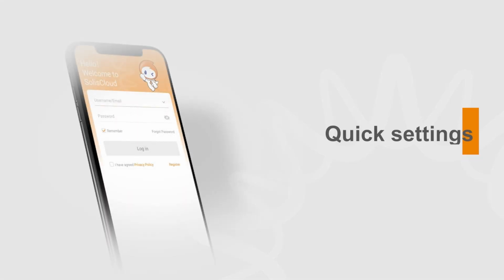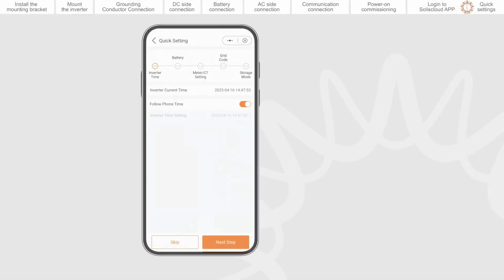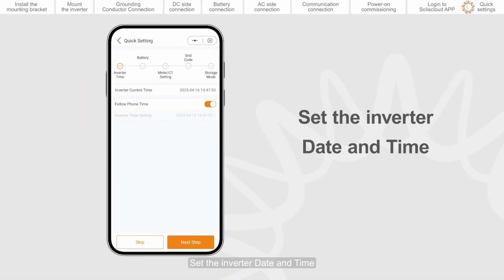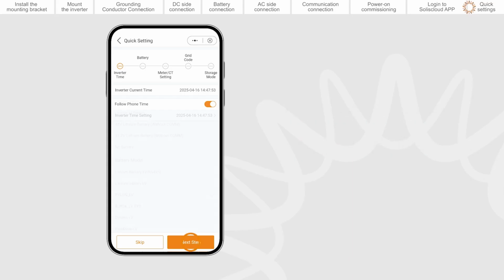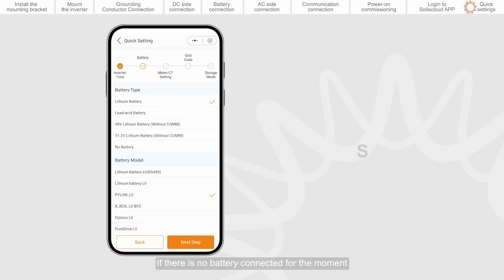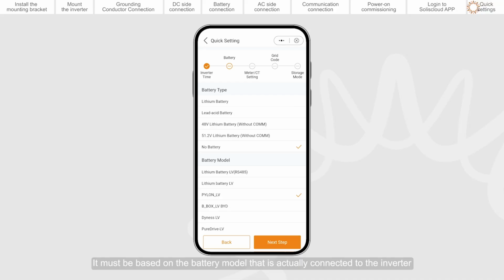Quick settings. Set the inverter date and time. You can set to follow phone time. Set the battery type. If there is no battery connected for the moment, please select no battery to avoid alarms. It must be based on the battery model that is actually connected to the inverter.